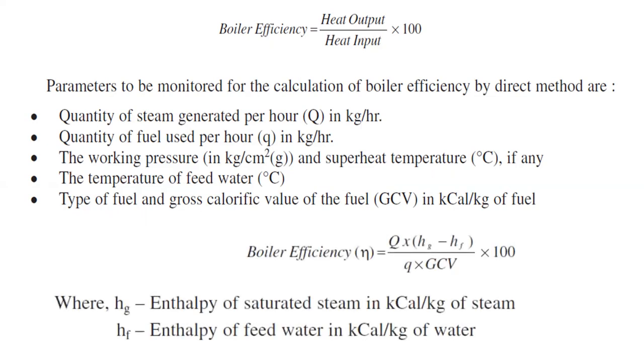In this method, boiler efficiency equals Q × (Hg − Hf) × 100 divided by Q × GCV, where Hg is the enthalpy of saturated steam in kcal/kg of steam, and Hf is the enthalpy of feed water in kcal/kg.